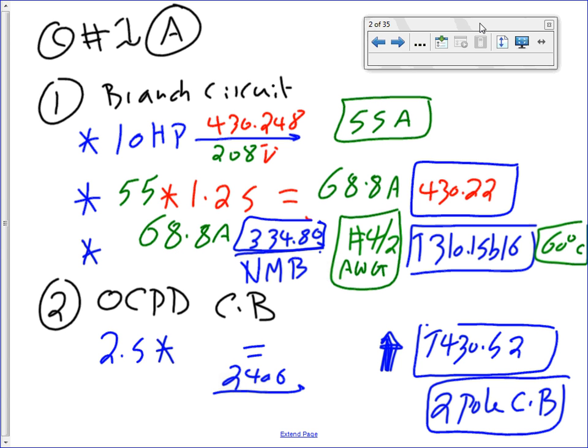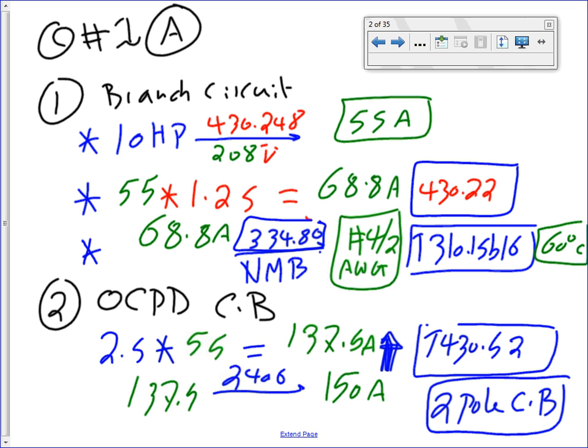Now the second thing that we need to do is size the overcurrent protection device. Same thing, guys. You take the 55, and multiply that 55 by 2.5. I'll tell you where you get the 2.5 in a second. That will give you 137.5 amps. The code book says if it's not a standard size, do not cry, go up. So you take the 137.5 to 240.6, you remember that, and that will get you a healthy 150 amp two-pole circuit breaker. Where do you get this info? 430.52, I'm sorry, 430.52.